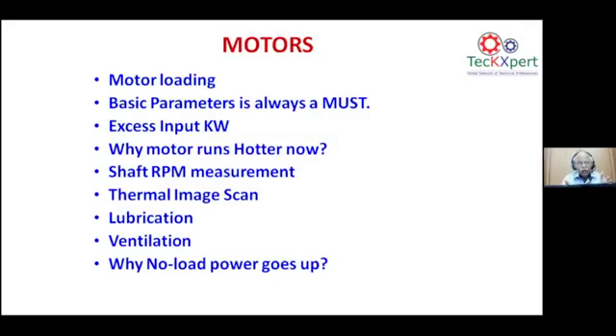By going for that, we are able to reduce the temperature of the motor by more than 20 to 30 degrees, and ambient plus 20 degrees is the allowable temperature for a normal healthy motor. That's what we want to see now. Then comes the ventilation, and why the no load power for the given motor goes up. Let us go step by step.